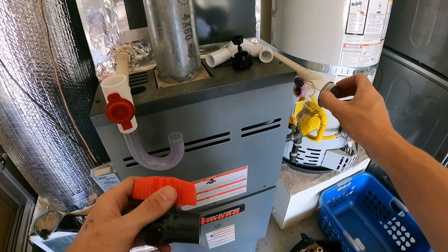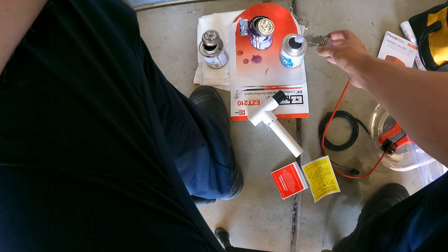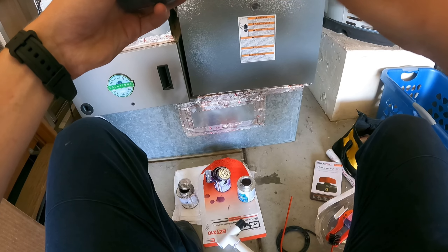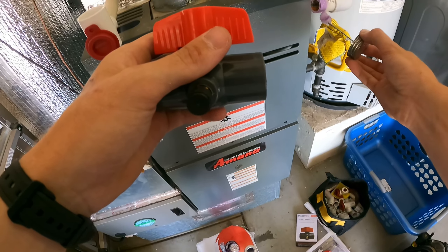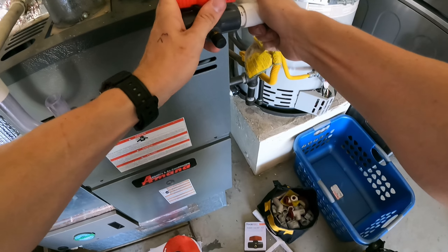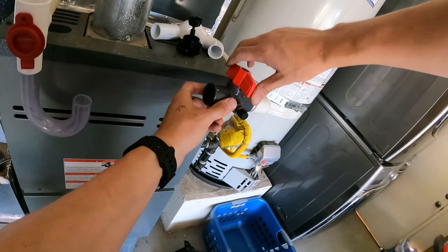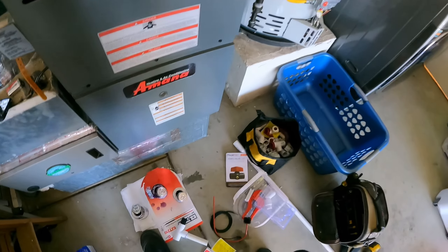Primer, primer, primer — and hit it with the glue. I always turn that valve a few times after gluing. I want to make sure there's no glue in there that would glue that valve shut, because that would defeat the whole purpose.